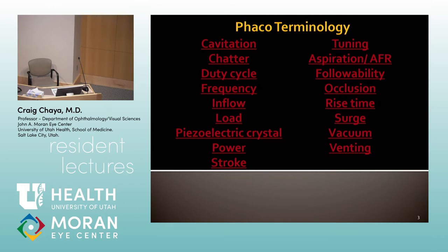So we got all the tough ones. The basic terms on the right side — first thing would be aspiration, which is essentially just your vacuum power, the amount of vacuum power. A lot of what you're doing in phaco is not actually using phaco power. You're using aspiration to bring pieces to you, and then you're using occlusion to move the pieces around.